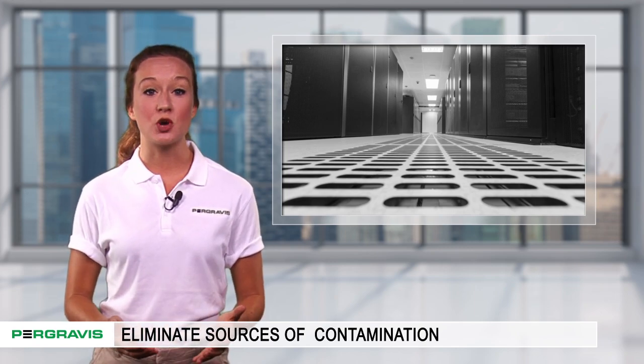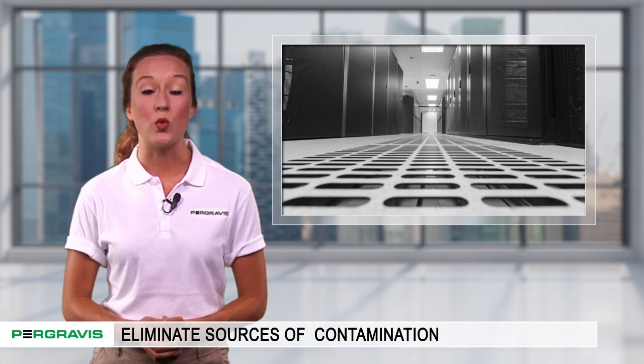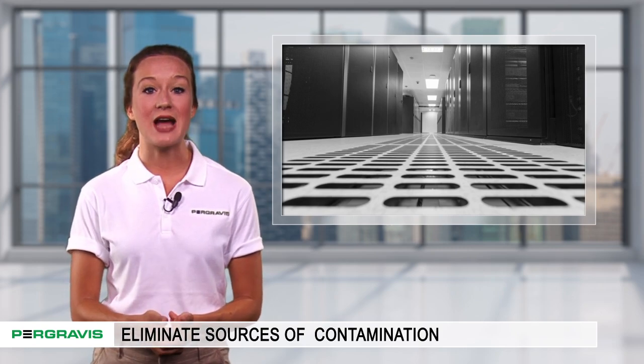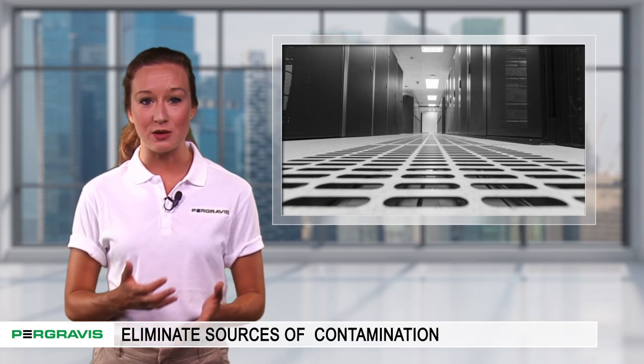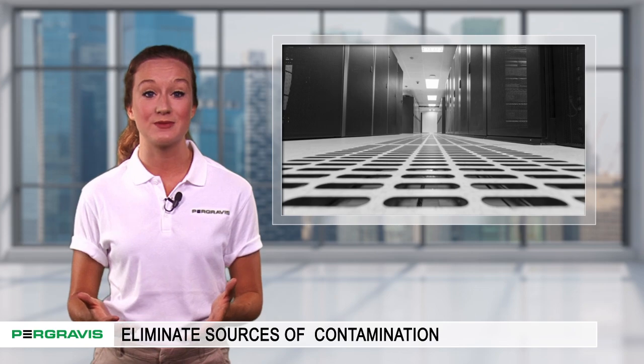Metals with a galvanized coating also can shed zinc whiskers. These conductive metallic fibers can find their way to circuit boards where they can create short circuits.